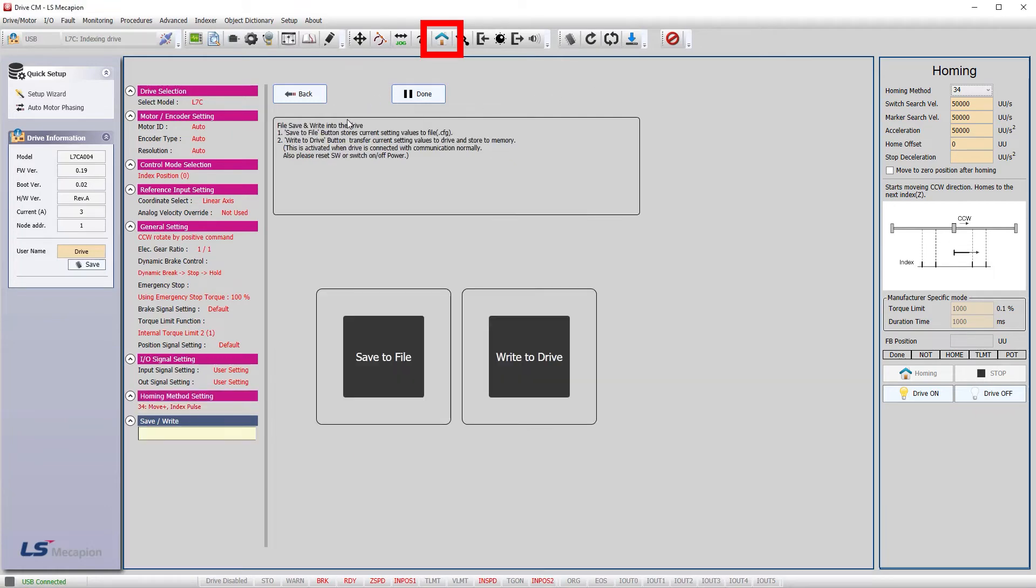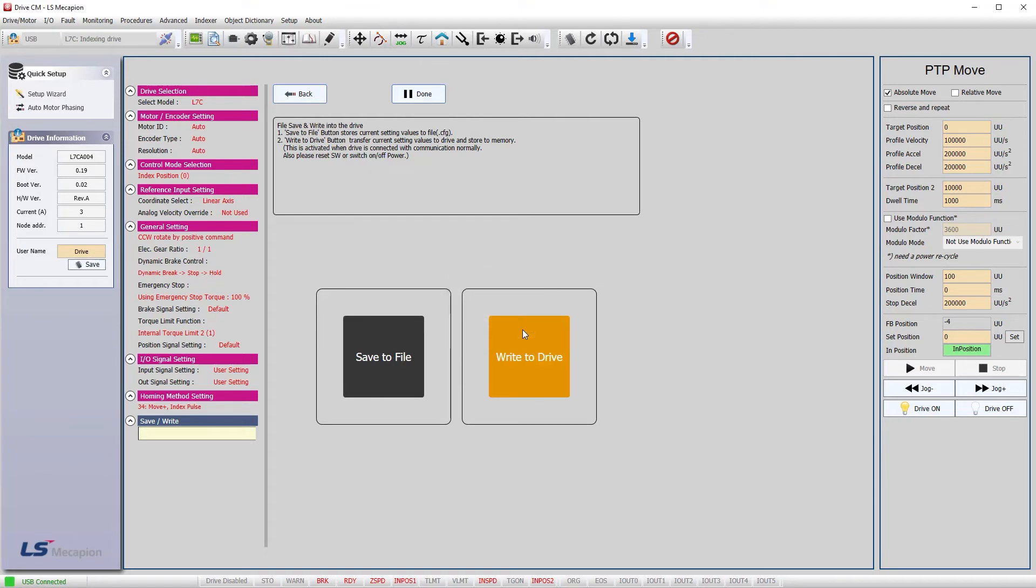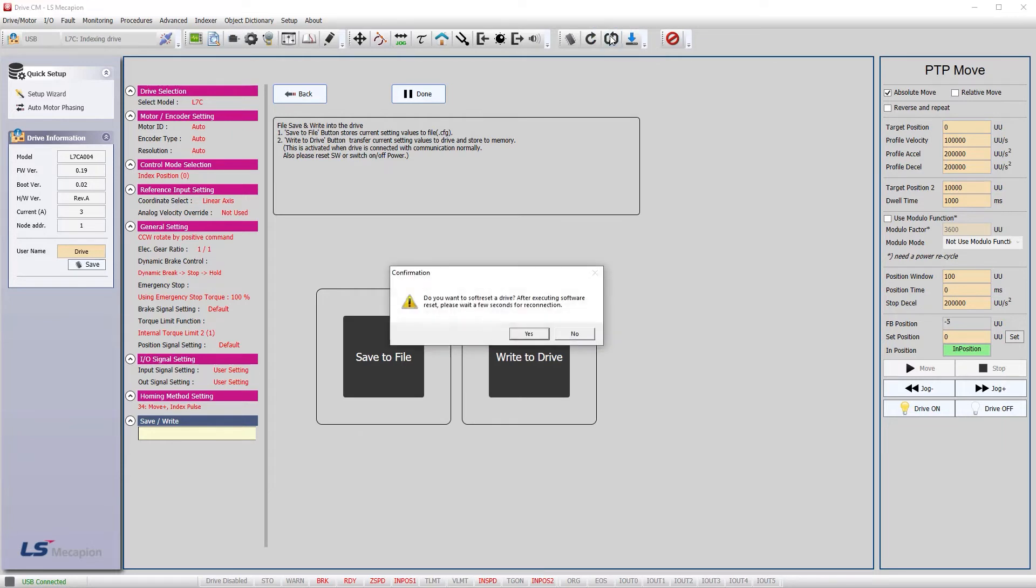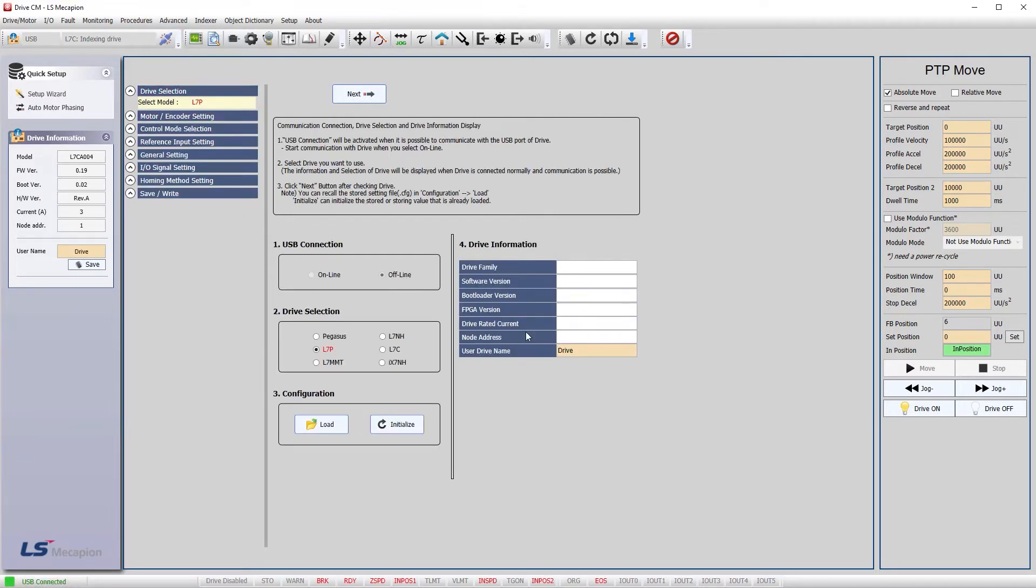And we're done. Make sure the drive is disabled and write the configuration to the drive. Wait for confirmation, there it is. Normally I would save this to file, but we haven't set up homing yet so I'll wait on that. And don't forget to do a soft reset of the controller after a write to ensure it has a fresh start with the new parameters. Wait for it to reconnect, got it.